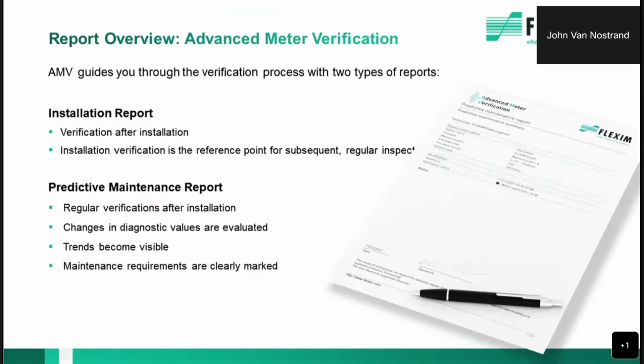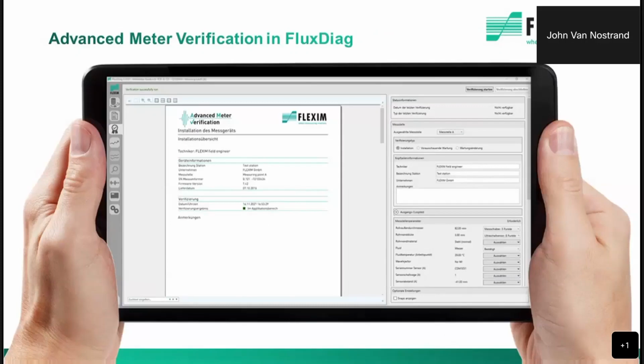Another thing that's important is the advanced meter verification. So what this does is this gives us a report of how the meter was when we installed it. We look at a lot of diagnostics and it saves this in the historian. And then when we come back to the meter, let's say at an annual calibration interval, we can actually look at those diagnostic values and we can see if anything has changed, if any trends have occurred or signal losses, etc. And then we have on our report an indication in green, yellow, or red to say that it's good, it needs to be attended to, or it has some kind of a malfunction.